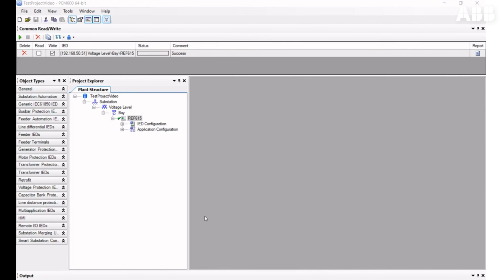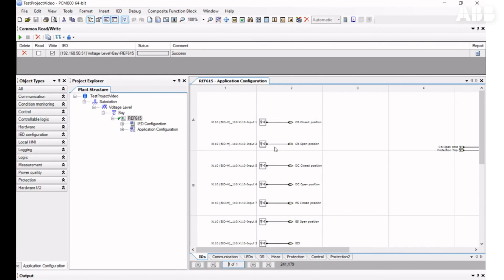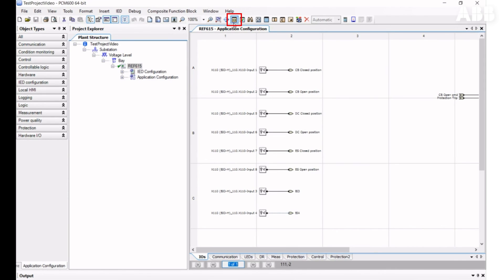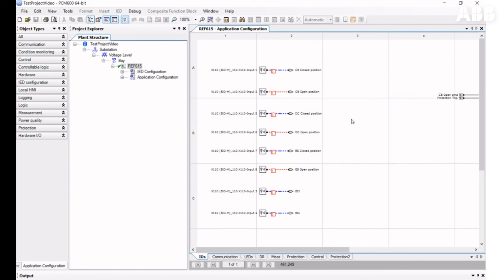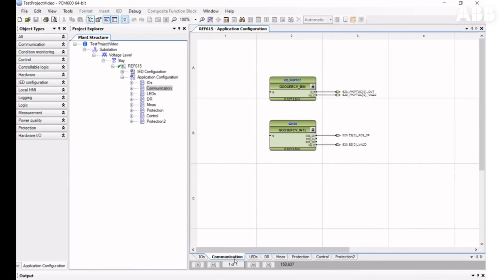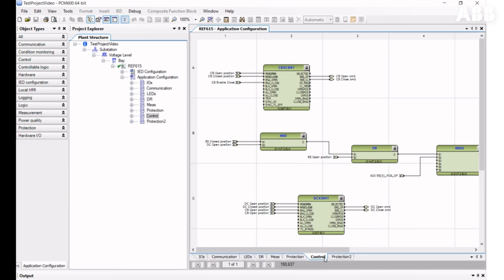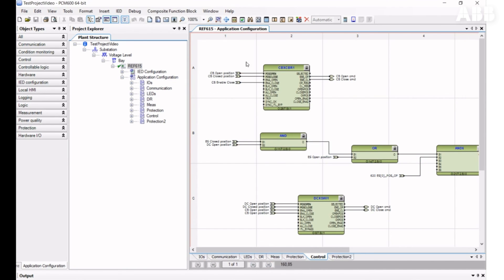When you have the same configuration on the relay and PCM600 and your computer is connected to the relay, you can use the Work Online function in the Application Configuration tool. To enable Work Online mode, open the tool and click on the Work Online icon. When this mode is active, you can see the online statuses of signals — a blue line means the signal is not active (false), and a red line means the signal is active (true). You may need to wait several seconds to see status updates when navigating. You cannot make changes to the configuration while online mode is enabled.